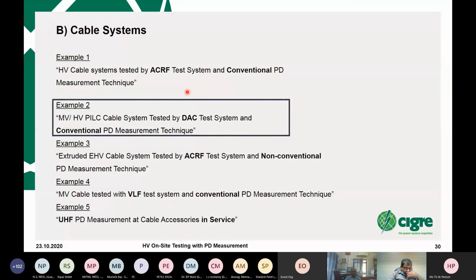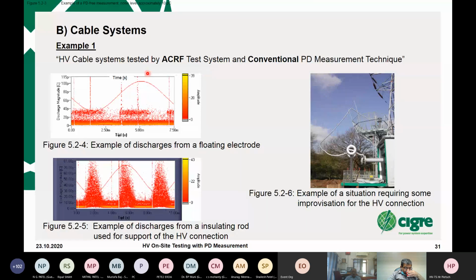So I will show example 1 and example 2. Example 1, on the left-hand side, you see the different PD defects. I don't want to go into this interpretation. This is shown in this brochure. I would like to show the tricky point on site. In this case, I chose this pattern picture because it's very tricky to get access to the cable joint in that part. And then you have an overhead line which is going into the cable, and you can see that and estimate that you can maybe pick up a lot of noise, and even the connection can produce PD corona and so on. So this is experience on how to connect, and in some cases there are physical large distances to cover. And so it's sometimes really tricky, and you need some good ideas to handle this.